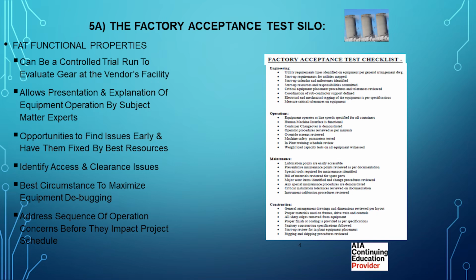Typically what I run into - if everything's done at factory witness testing, I'm very satisfied. They ship it to the field, I do another inspection to make sure everything's still the same. But as soon as subs and vendors and everyone else start getting their dirty fingers in there, anything that's not sealed and has been tampered with, I've got to go back and inspect and test anyway, regardless.